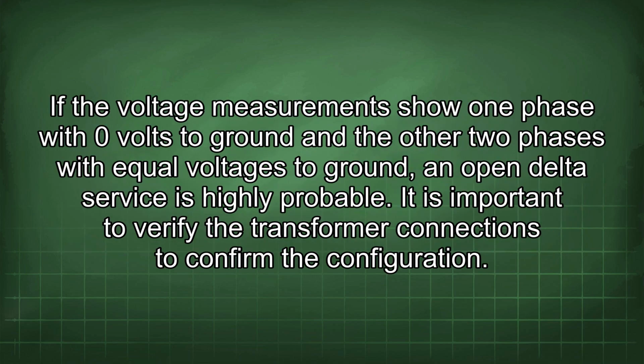If the voltage measurements show one phase with 0 volts to ground and the other two phases with equal voltages to ground, an open delta service is highly probable. It is important to verify the transformer connections to confirm the configuration.